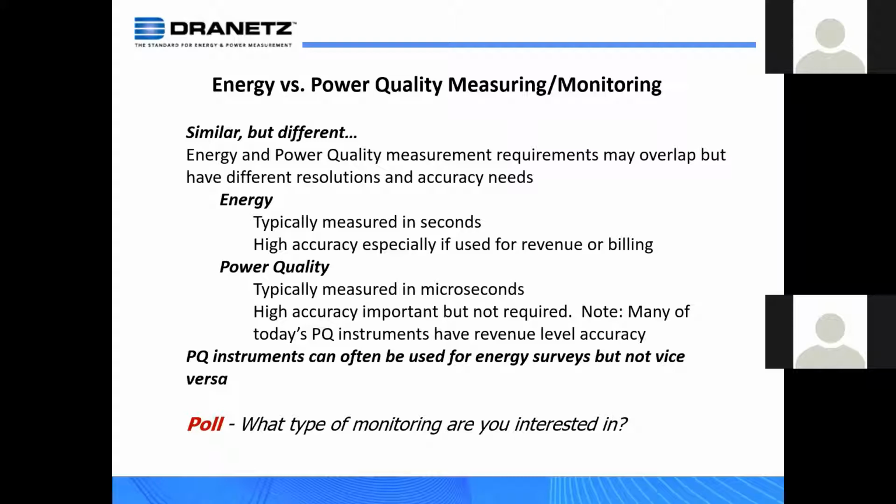So for the sake of this web meeting here today, we're going to use a generic term, power monitoring, because a lot of the application and rules of thumb apply to both power quality and energy. But they are different tools at their heart. So it's important that we understand the difference between an energy meter and a power quality meter that could also have energy capability. So their measurement requirements overlap, but they have different resolutions and accuracy needs.